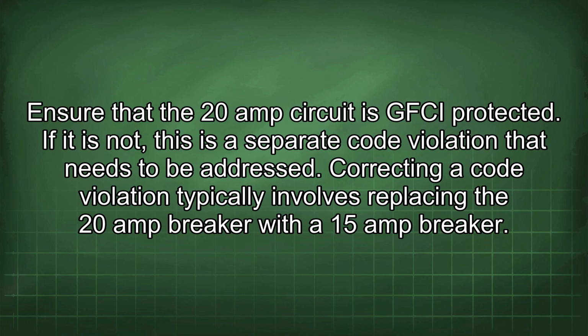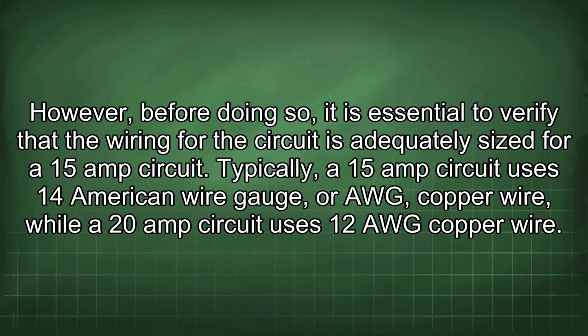Correcting a code violation typically involves replacing the 20 amp breaker with a 15 amp breaker. However, before doing so, it is essential to verify that the wiring for the circuit is adequately sized for a 15 amp circuit. Typically, a 15 amp circuit uses 14 American wire gauge, or AWG, copper wire, while a 20 amp circuit uses 12 AWG copper wire.